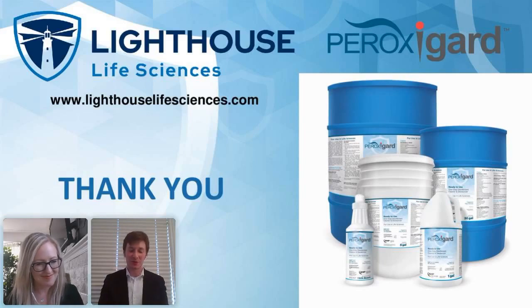Yeah, we're definitely able to help with that on our end as much as possible. So basically, we'd work with you to set up that cleaning and disinfection protocol to get those baseline readings. And then it would be a combination of us working with you on that, as well as guidance from the meter manufacturer on setting up the limits. Different meter manufacturers have different recommendations. Some will say to take a certain number of readings and then do an average. So there are different formulas that they might use, but we can definitely help support from the aspect of setting up the cleaning and disinfection protocols to actually do this process.